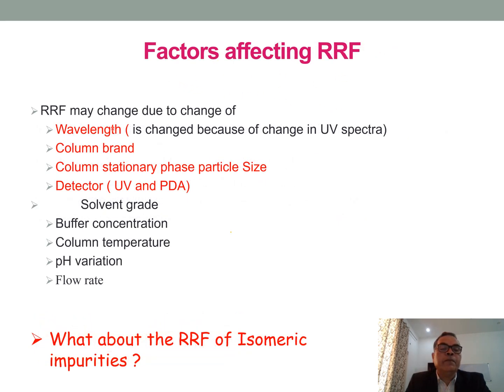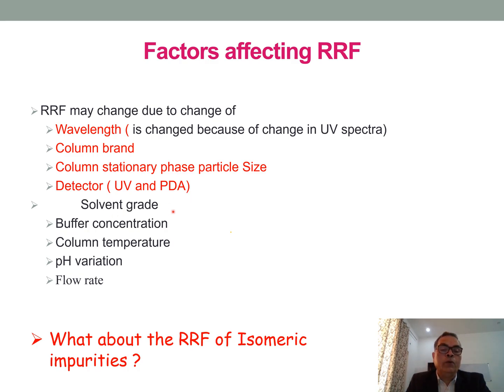Factors affecting RRF: RRF may change due to a change of wavelength. When the wavelength is changed, the UV spectra will change and hence RRF will change. Other factors include: column brand, column stationary phase particle size, and detector type. For example, if a method was developed on a UV detector and the analysis is performed using a PDA detector, then RRF will vary. Additional factors include solvent grade, buffer concentration, column temperature, pH, and flow rate.